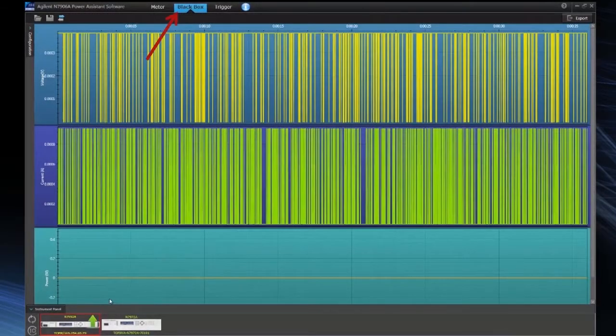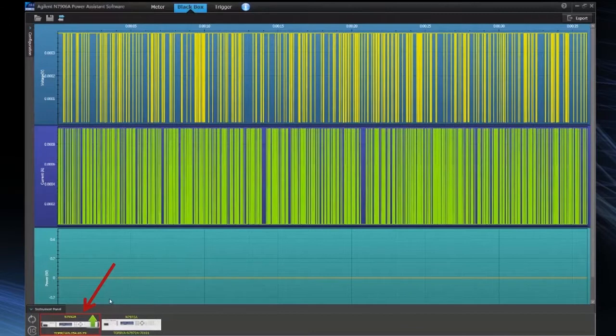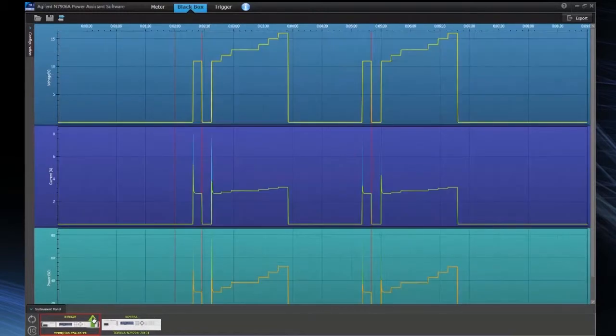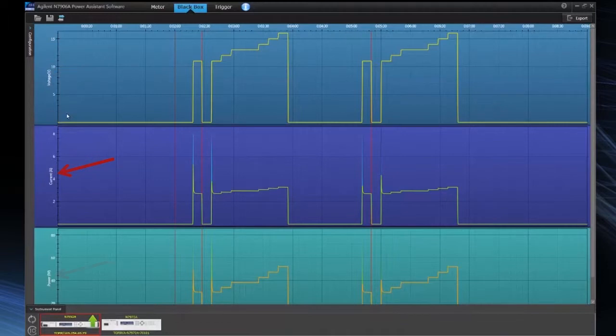Now we're looking at the black box recorder analysis view of the Power Assistant software. So let me first upload data from the black box recorder on the one kilowatt power supply. So now we can see with time stamps voltage, current, and power measurements.